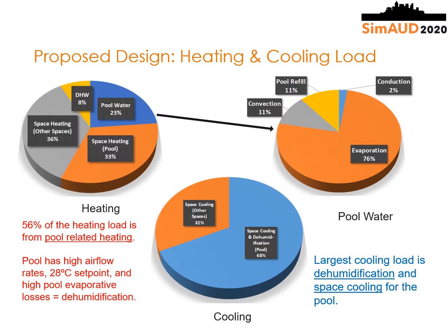Here is the breakdown of the heating and cooling load for the proposed design. For heating, 56% of the heating load is from pool-related heating, and that is because the pool has a high airflow rate and it has a high heating set point of 28 degrees Celsius and high pool evaporative losses, which leads to high dehumidification levels. For cooling, the largest load is dehumidification and space cooling for the pool. In summary, the pool is a big energy consumer in this building.